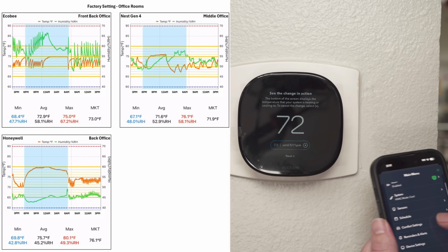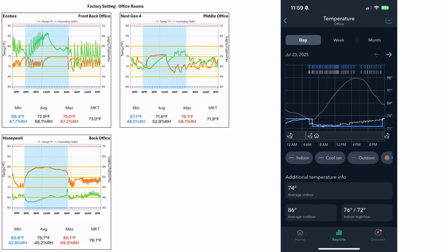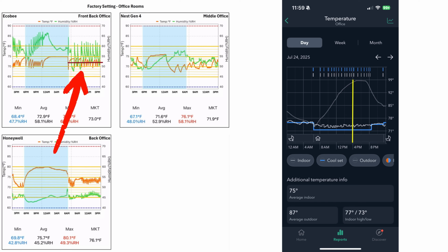And from there, I made no other changes. So we can see that the Ecobee did pretty much the same thing as the day before. What's going on the right-hand side of the screen is the Ecobee's thermostat report, showing us the thermostat set points. So you can see that it did average around 72 degrees until 11:30. Then after that, it went into sleep or away mode or whatever mode it went into and jumped up to 75 degrees. Then came back on at 72 degrees when the first person entered the office at 6 a.m.